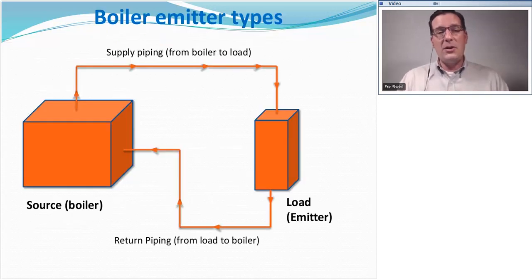Next, we're going to talk about emitters. And the emitters is where the heat leaves the system. Another word for emitter is load. Another word for boiler is the source. So the source or the boiler, this is the heat source of the whole system. This is where heat enters the system. The load or the emitter is where heat leaves the system. There's a lot of different kinds of emitters out there, and they could be mixed and matched in a single installation. So this is one of the important things that you need to get down first when you're looking at a new boiler system: what type of emitters are we working with here?